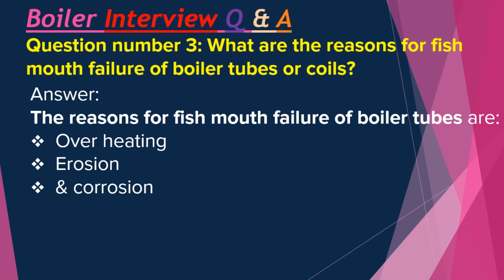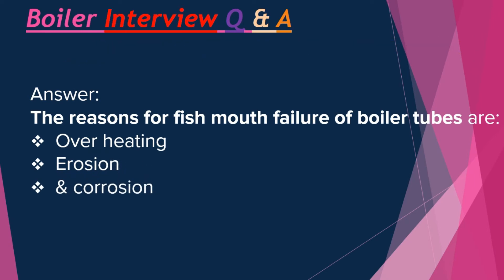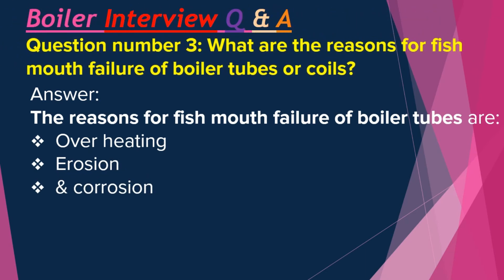Question number three: What are the reasons for fish mouth failure of boiler tubes or coils? Answer: The reasons for fish mouth failure of boiler tubes are overheating, erosion, and corrosion.